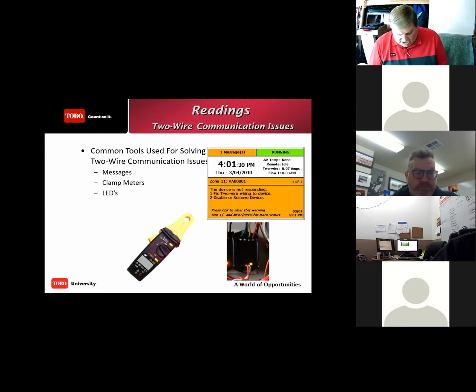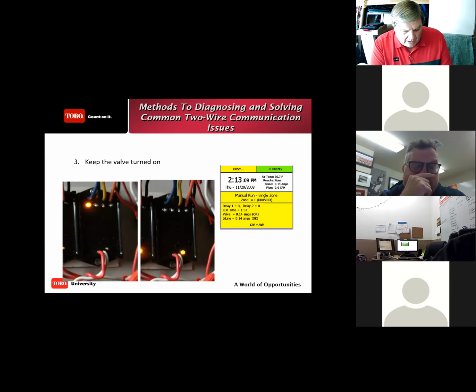One, check the connections for loose wires. Check that the connection is not corroded and not shorting out. Using your clamp meter, here's another type of clamp meter. Again, it must be a leakage testing device, okay? A leakage current tester.